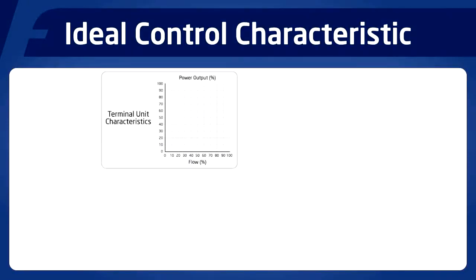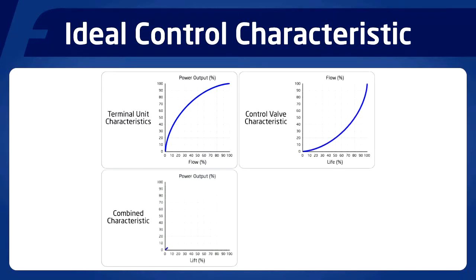Because a typical heat exchanger, such as an air handling unit, generally has an equal percentage relationship between flow and power output, as can be seen in the top left hand graph here, it is necessary that the valve and the actuator combination also have an equal percentage characteristic, but this time in the opposite direction.